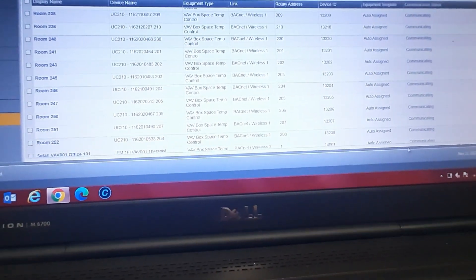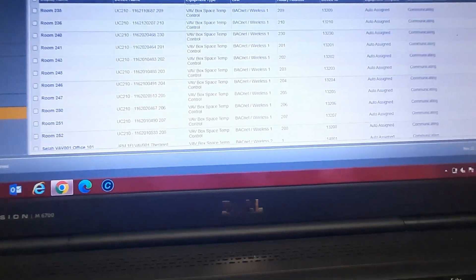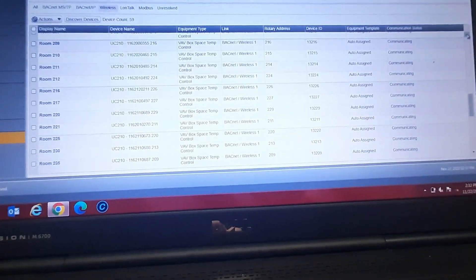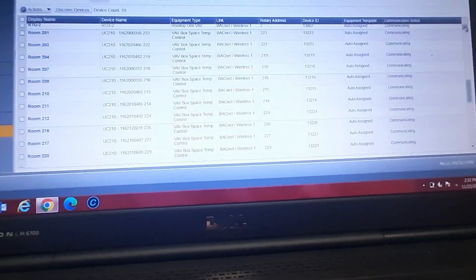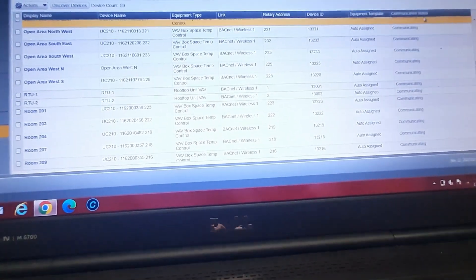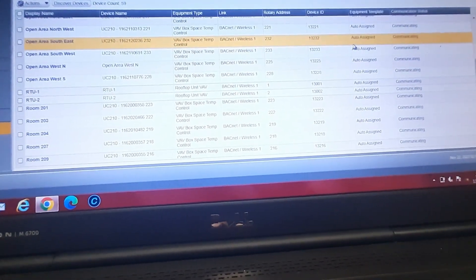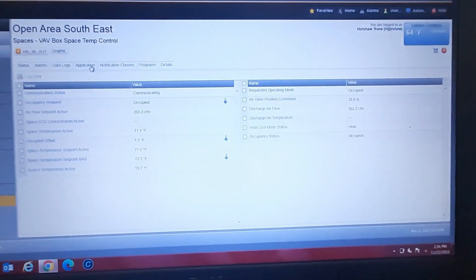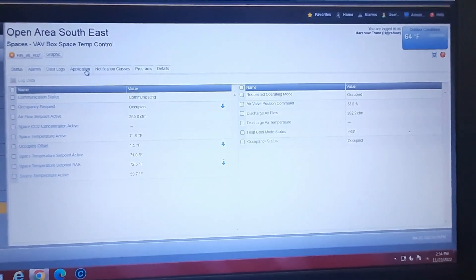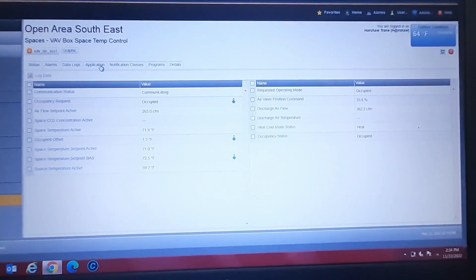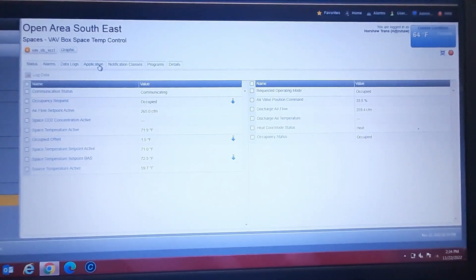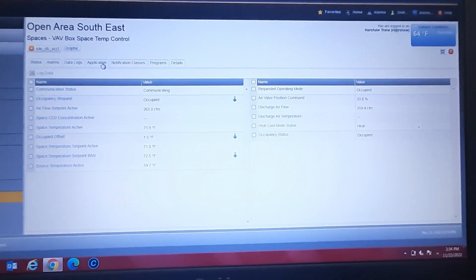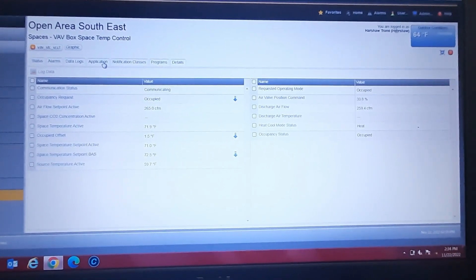So I located 206. So I got room 250 and then 232 is here somewhere. So room 250 and open area southeast. I'm looking at this box, it looks like it doesn't have a discharge air sensor or it's not reading. It is in heat mode, space temperature is 72, set point is 71. Now I noticed he had this thermostat set on 74, 75.